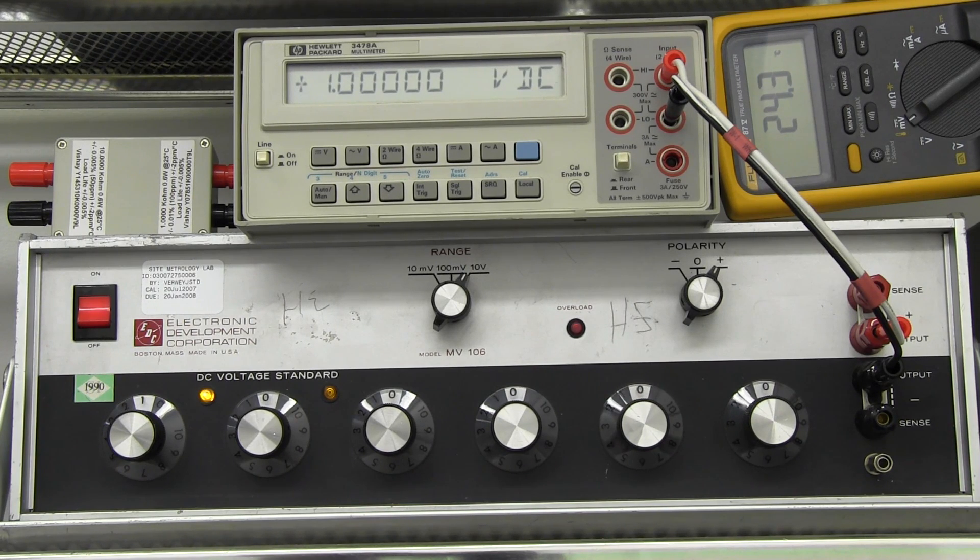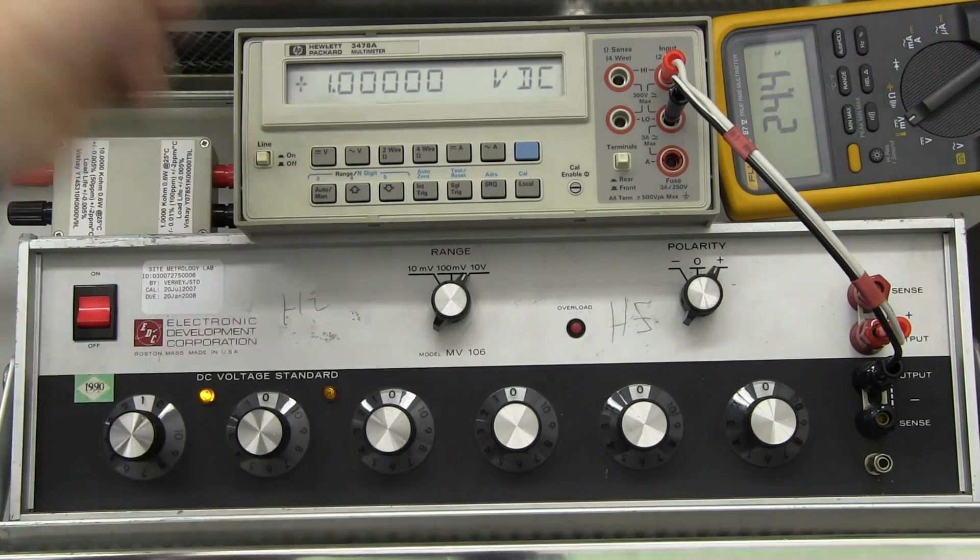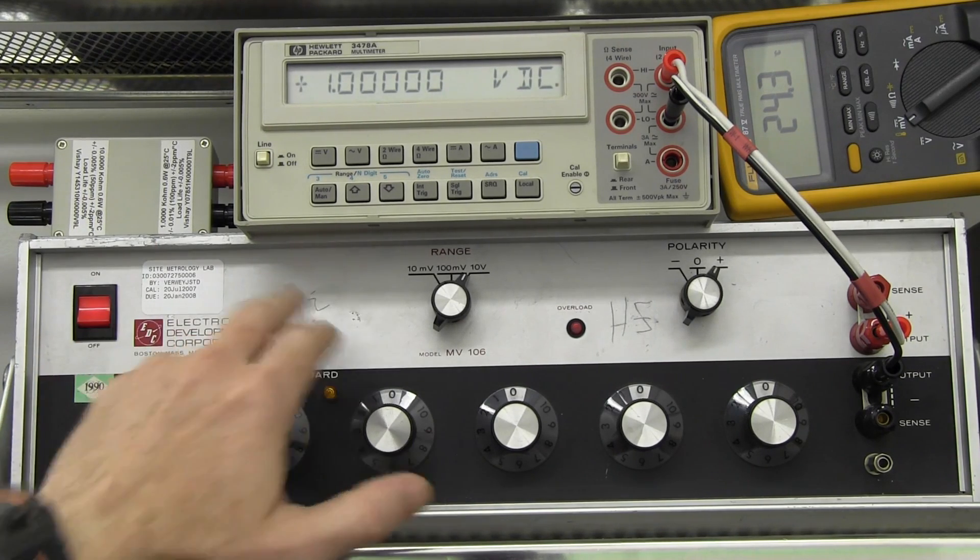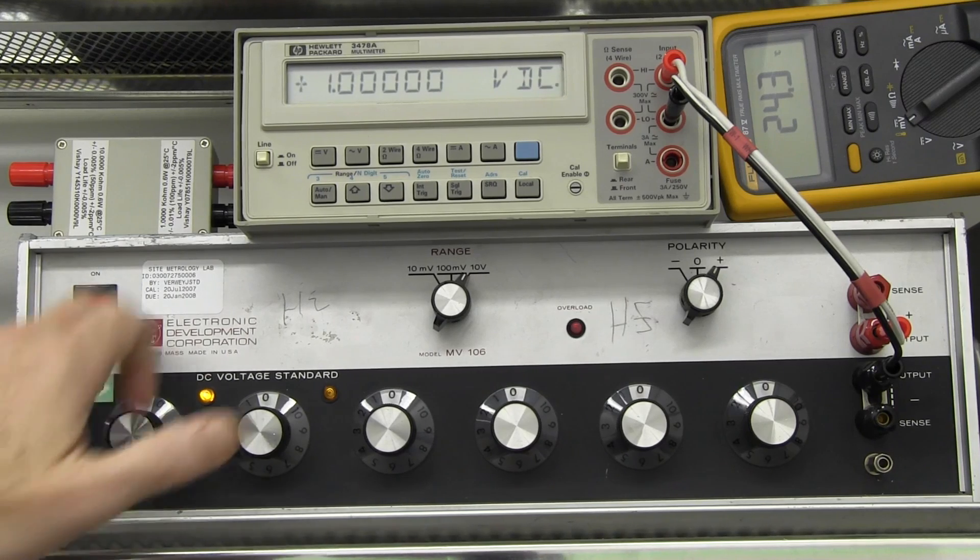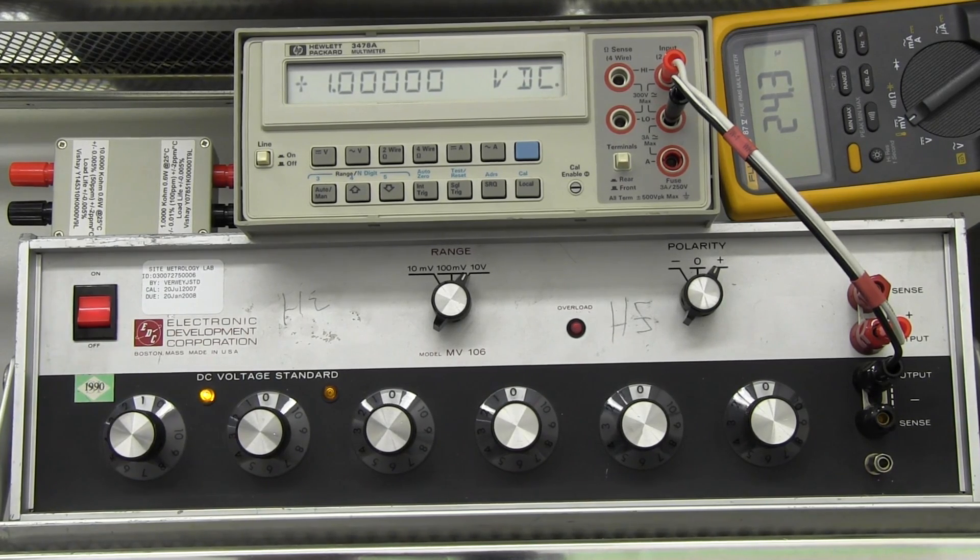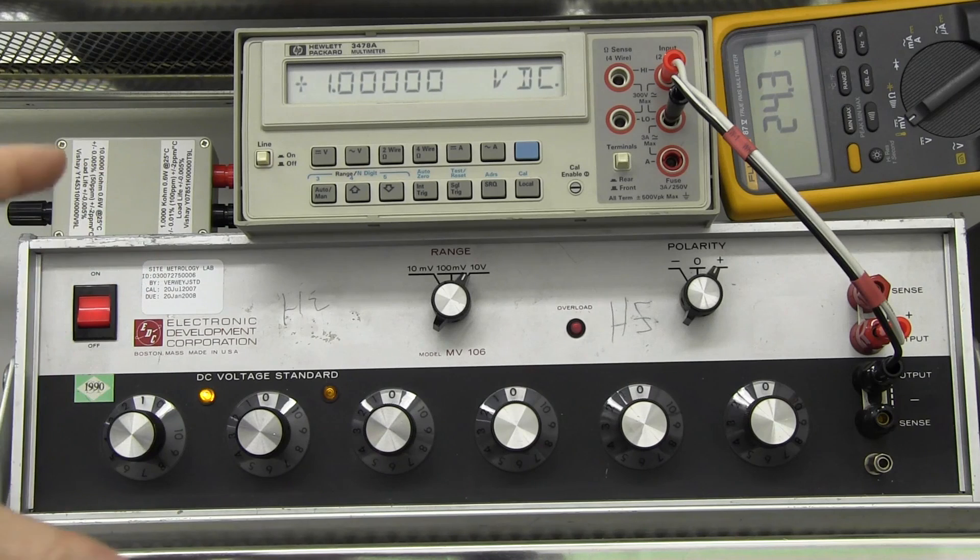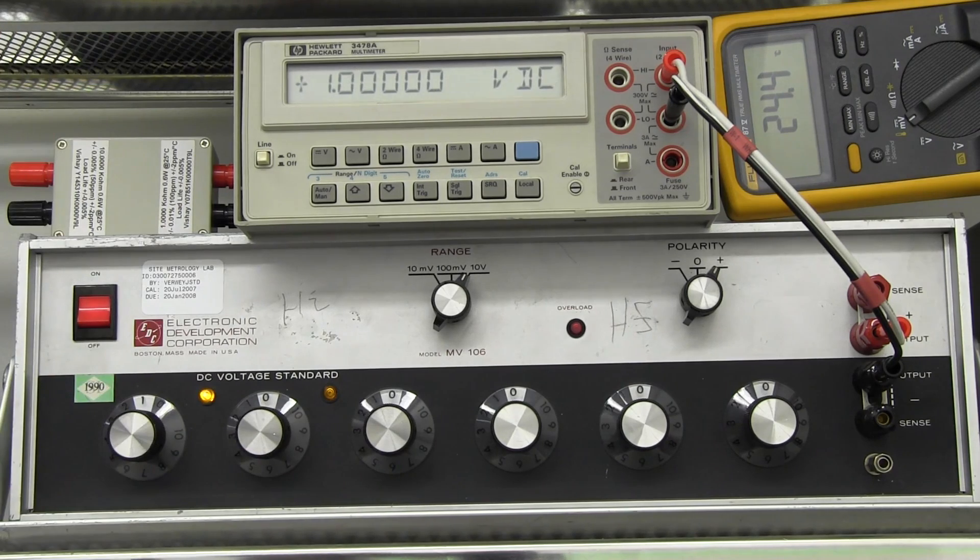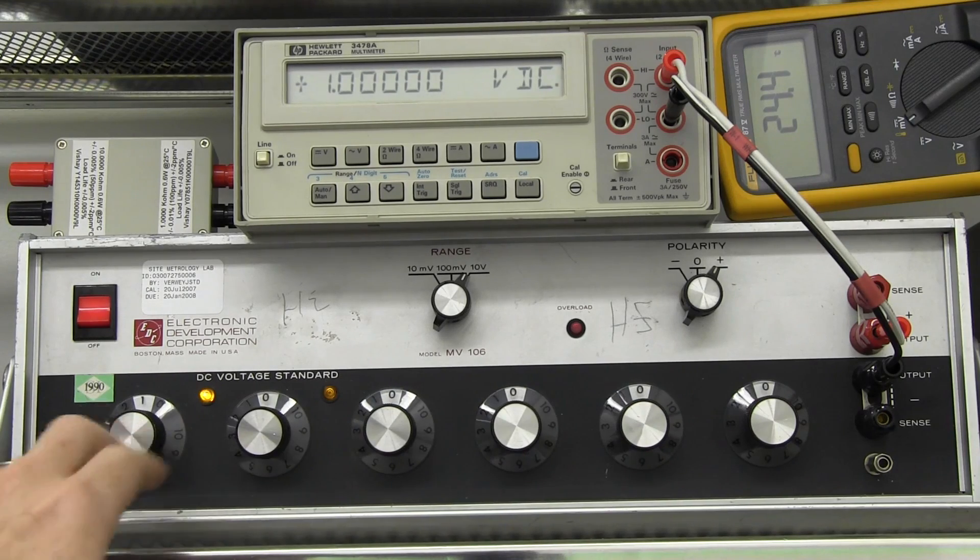This might be an in-depth tutorial as well. I just wanted to show off my little transfer standard here, my HP 3478A. I'll link in the video to this EDC Electronic Development Corporation MV106 DC voltage standard that I've got. I bought this for like 20 bucks on eBay. It was an absolute bargain. And I took it to the local calibration laboratory Trio Smart Cal. They're just down the road here. And I'll link in the video to that and you'll see that this was actually absolutely spot on. It didn't need any adjustment whatsoever. And it's a six decade device so I can adjust it.